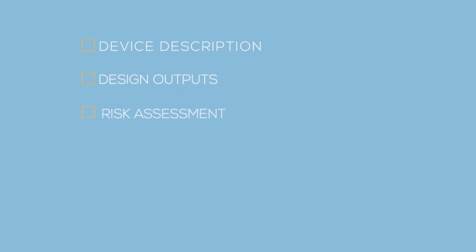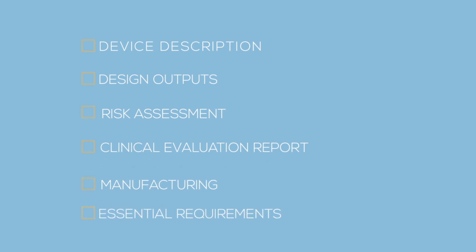It includes the general description of the device, design output documents like specifications and drawings, risk analysis of the design and relevant manufacturing processes, the clinical evaluation report, the manufacturing methods envisaged for routine production, and a description of the technical solutions to fulfill the essential requirements, including material selection, biocompatibility, electrical safety, electromagnetic compatibility, sterilisation, packaging, and labelling.